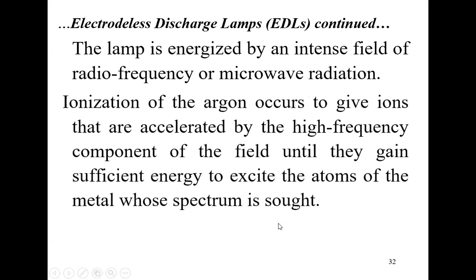Now, the lamp is energized by an intense radio frequency or microwave radiation. And again, it works on the same principle as the hollow cathode lamp. The ionization of the argon occurs to give ions that are accelerated by a high frequency component of the field until they gain sufficient energy.